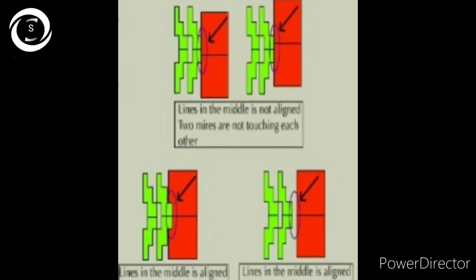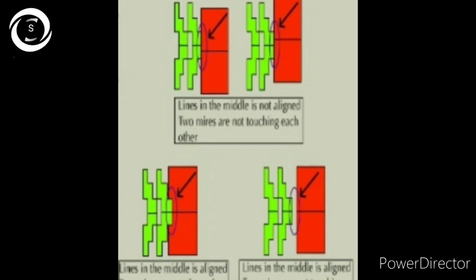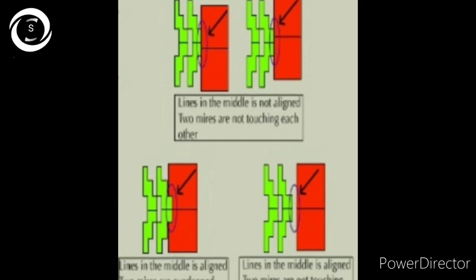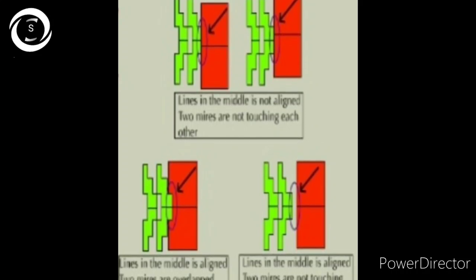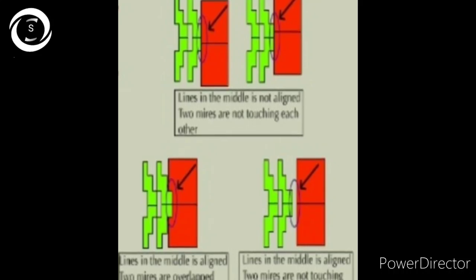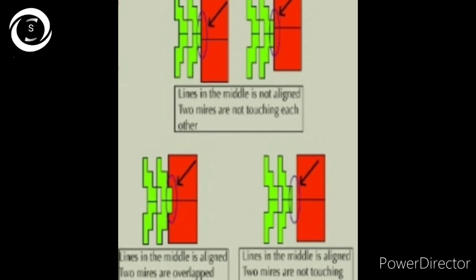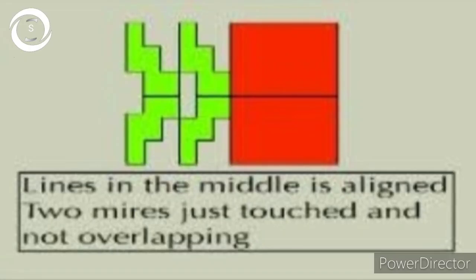In the above image, you can see the central line is not properly aligned, which will give you a false reading. If the mires are not touching each other, it will give you false readings. If there is a space between the two mires—rectangle and steps—it will give false readings. If there is overlapping of the mires, that will also give false readings. There should be no space, no overlapping, and the line of both mires should be continuous to get correct readings.